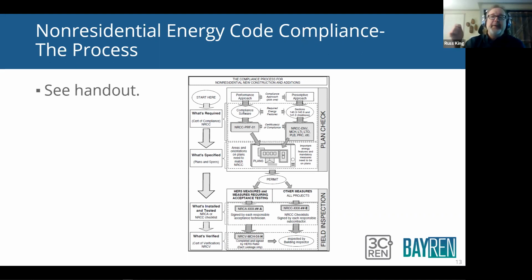I mean, you don't just want to plug in the lights, hook up the wiring, hook up the controls and walk away. You want to make sure those controls work. Make sure that they turn on at the right time, that the occupancy sensors work, that any kind of daylighting controls are sensing the right amount of daylighting before they turn off and things like that. So that's all acceptance testing. They don't expect building departments to do that, but it's a really good idea. It's very important if building departments make sure that those acceptance tests and those HERS verification forms get completed.